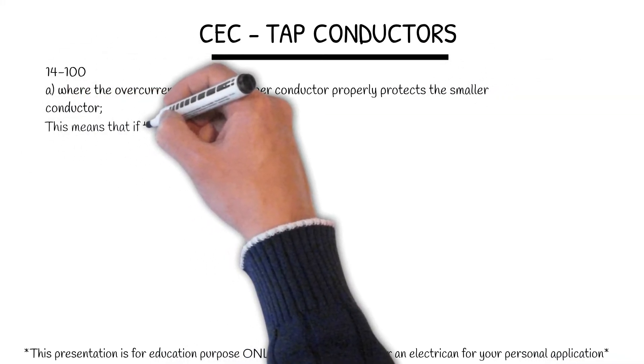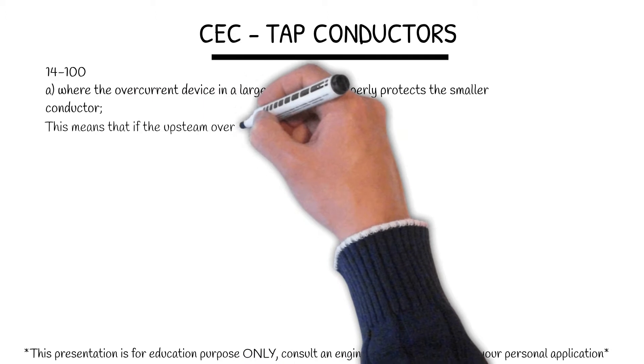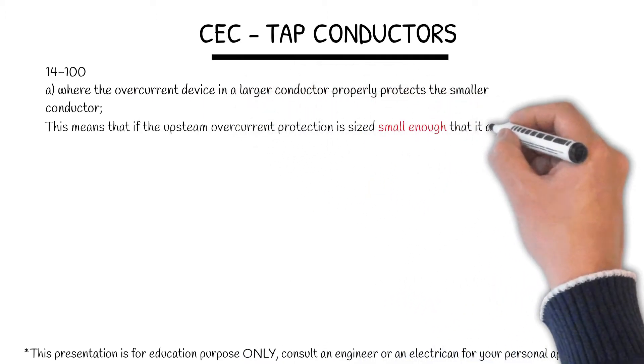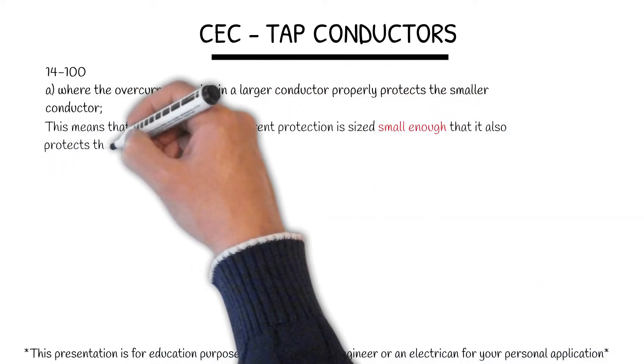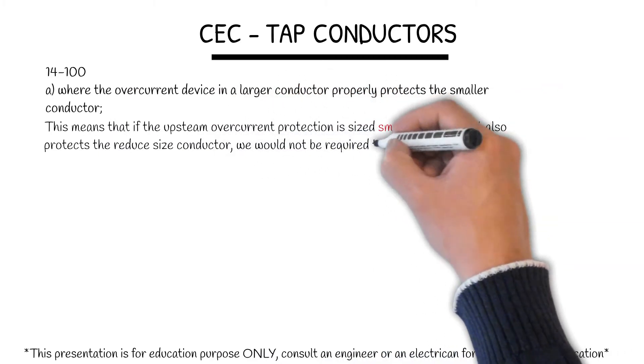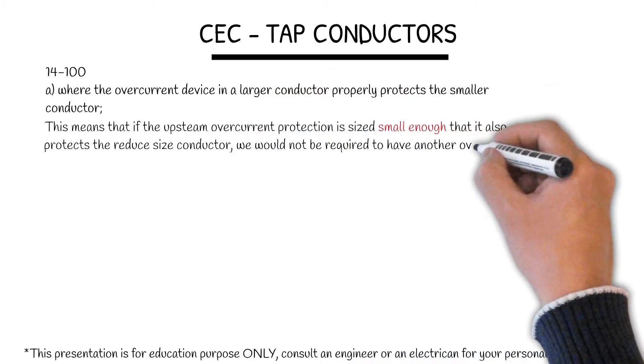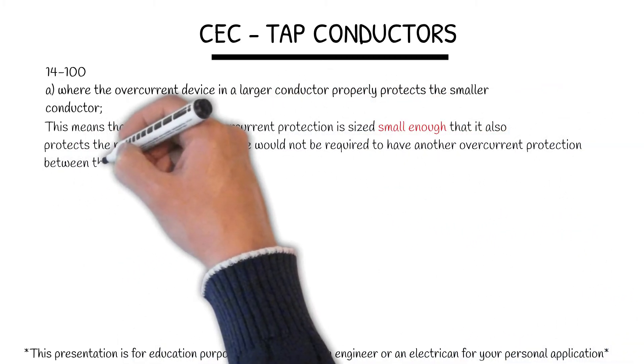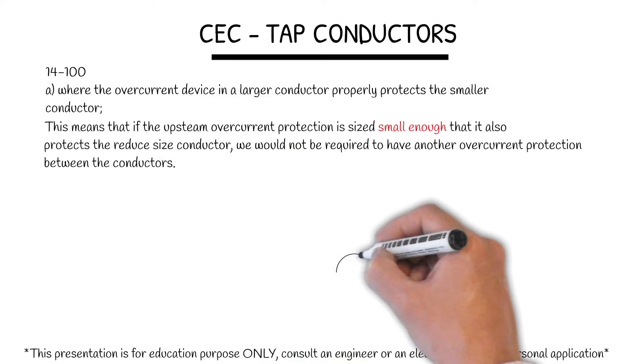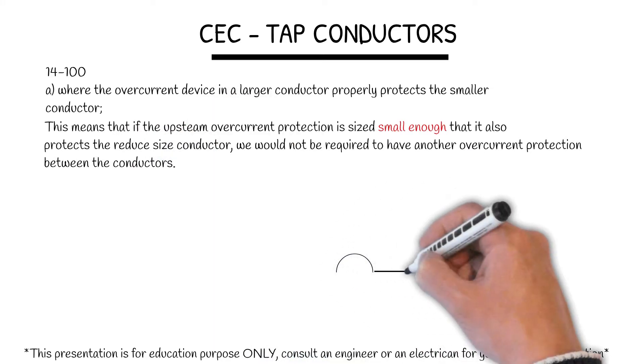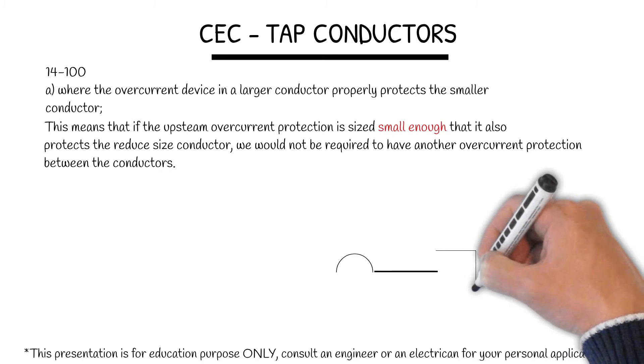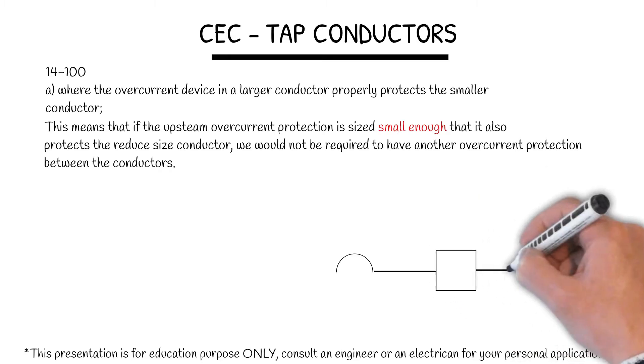This means that if the upstream overcurrent protection is sized small enough that it also protects the reduced size conductor, we would not be required to have another overcurrent protection between the conductors. Let's look at an example here that will illustrate this statement.